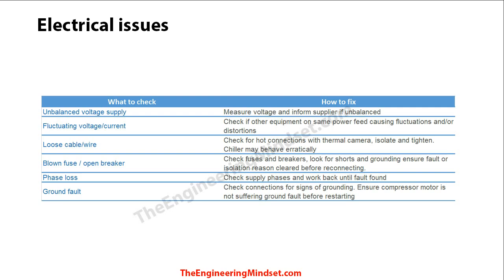Loose cables or wires are another issue — more common after a shutdown where work has been done and connections haven't been re-tightened properly, causing erratic chiller behaviour. An easy way to check for this is to use a thermal imaging camera on all connections — if any screws or terminals appear warm, that indicates a loose connection.